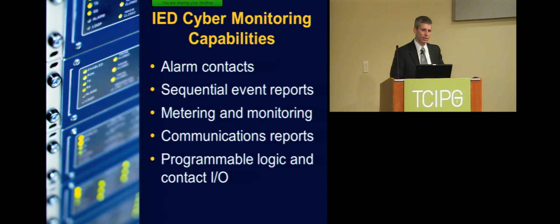And so there's things called alarm contacts on the devices, and it kind of sounds like an old technology. Essentially what it is, it's an electromechanical relay, and when the relay or the IED turns on, it opens up the contact, and if I were to lose power to the device, or the device's power supply stops working, the contact closes. Typically what is done is you map that contact output, that physical contact, to say an RTU or some other signaling device, and it can transmit the status of that IED back to an operations center. And historically what a lot of people have used them for is just for that signaling. The device is healthy or the device is not.